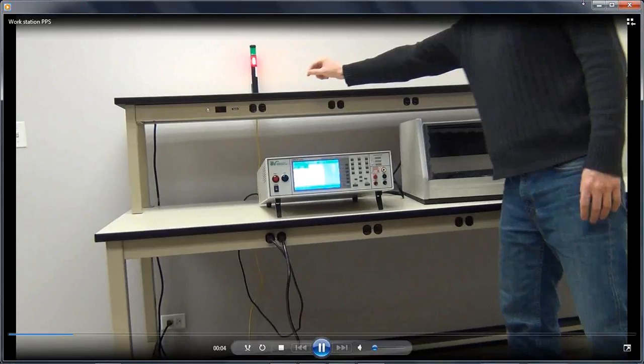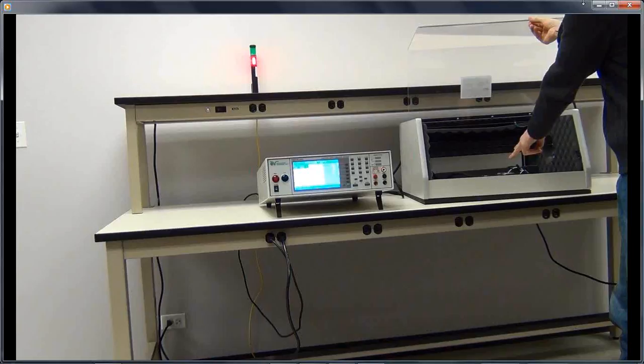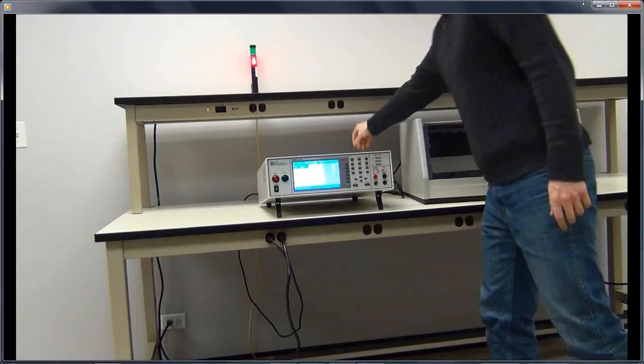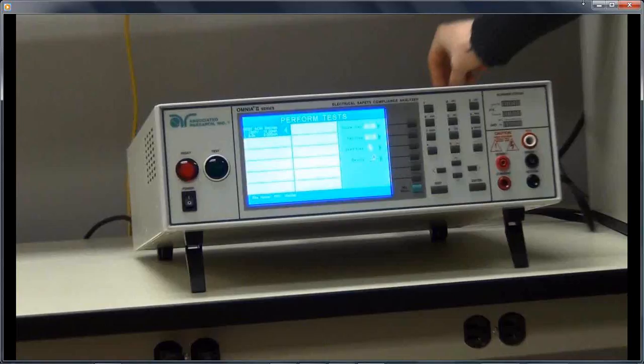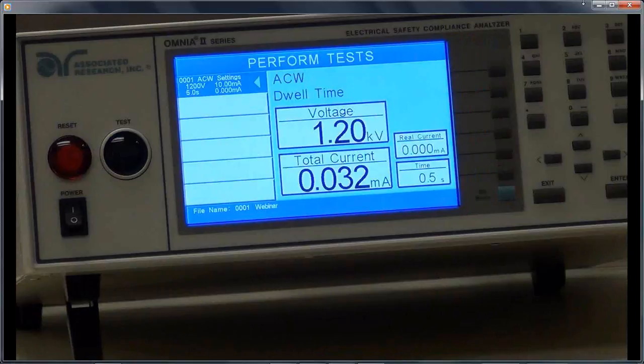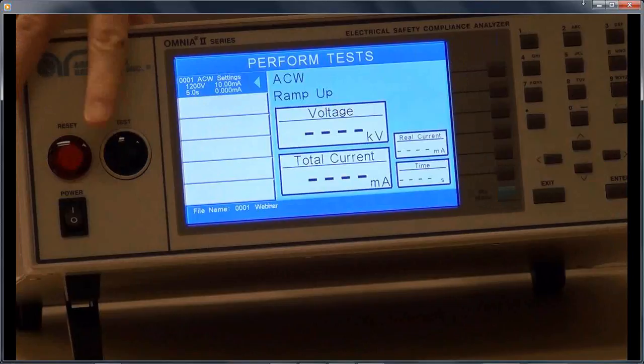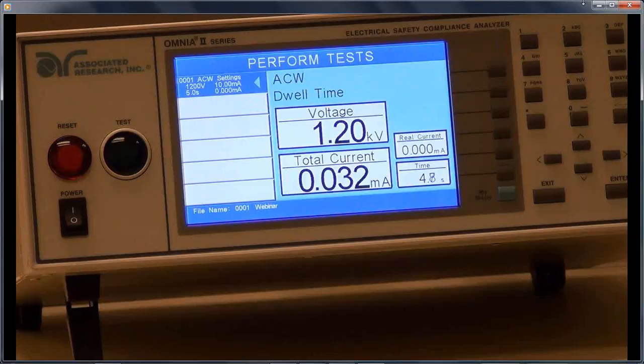So what we have here, you can see I have my signal light, it's on. I'm just leaving it red and on because the hipot is on. Here's a DUT enclosure, and that door is wired up to the rear panel of this testing equipment, going right into the back, because in the remote I/O of our instruments we have an interlock, so that's wired up to the door. So what happens is if I start the test and then open the door, breaking that contact, it's going to abort and let you know your interlock is open, and testing is immediately stopped. So I can reset that, test again, and as you can see, if I leave the door closed, the testing continues with no problems.